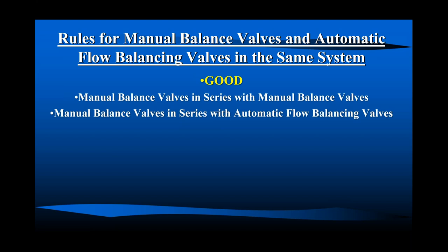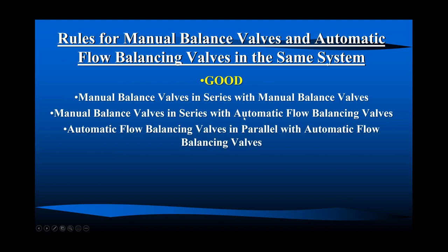Right, we start with the radiant manifold. Each loop, if you will, each tubing that goes into the floor, has a manual balance valve on it. But at least we know what flow is going to the whole entire manifold via an automatic flow balancing valve. Automatic flow balancing valves in parallel with automatic flow balancing valves. That is the basic full automatic flow balancing valve system.